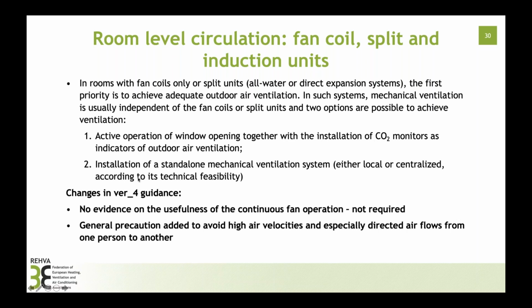And then indeed another, heavier option is installation of a mechanical ventilation system, where outdoor air ventilation will be assured. In the first versions of our guidance, it was recommended to stop these fan coil or split units, but no evidence supporting this has been found. So the latest versions of the guidance no longer include this recommendation. This has been changed. The main recommendation is to ensure outdoor air ventilation, and then it's not a big deal whether these units are operated or not. This goes according to the heating and cooling needs.